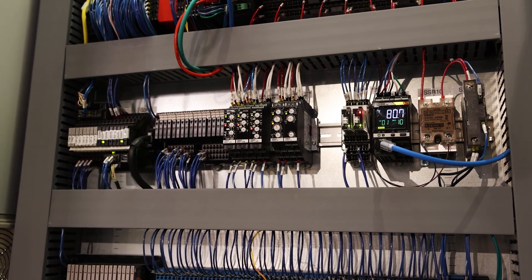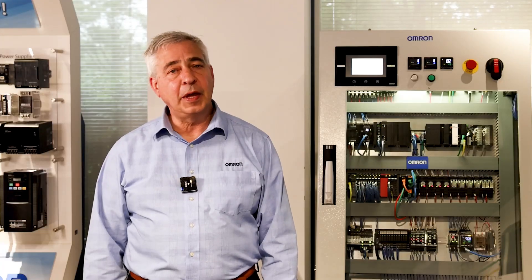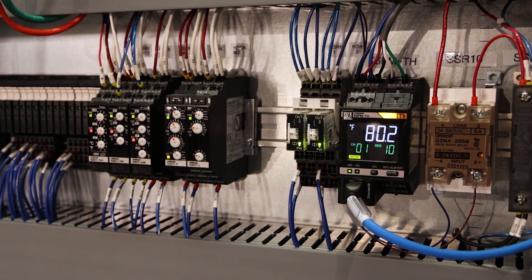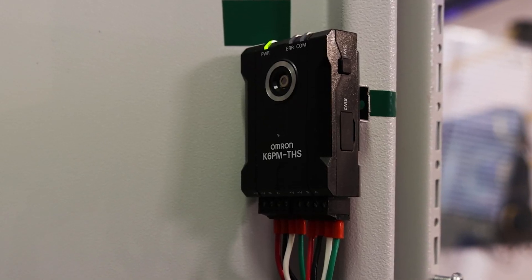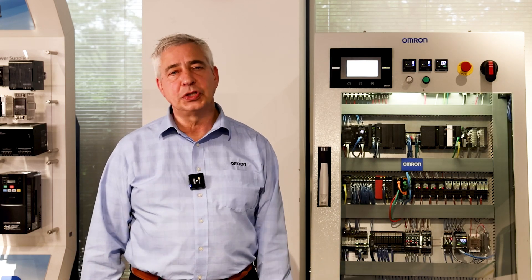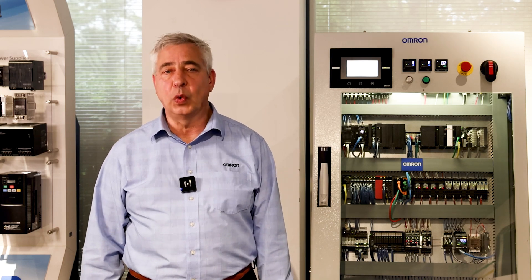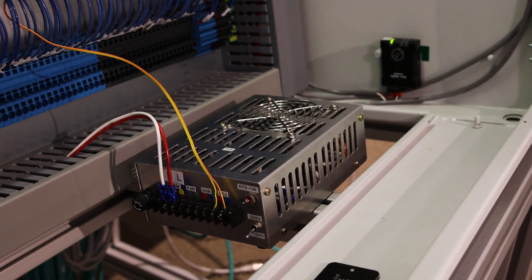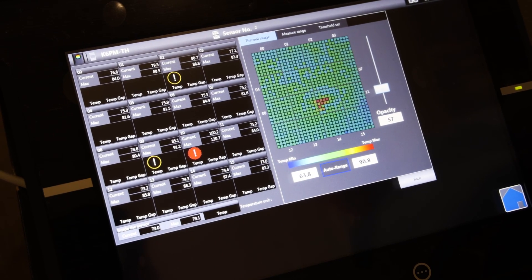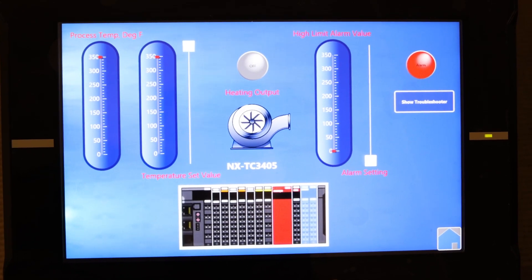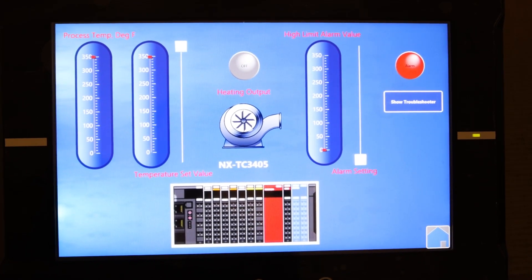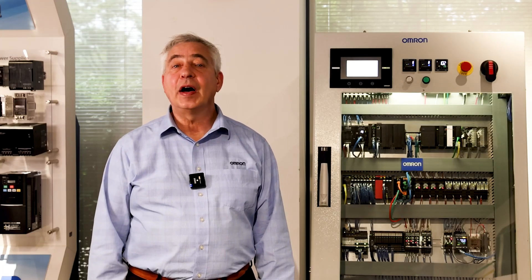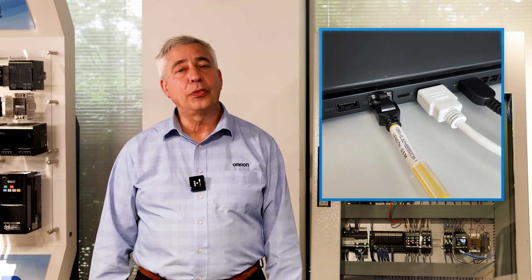The industrial controls in the demo panel are functional and generate heat. The internal panel temperature is monitored with a basic temp control and cooled if needed. In our panel, we have mounted and wired a K6PM-TH controller and two K6PM-THS thermal imaging cameras. Up to 31 cameras can be wired to a single controller, and the cameras can be placed 500 meters away. We use an NX-TC module with a solid-state relay and a heater element with thermocouple to create a hotspot. We use an NA5-HMI to control and display information. We've written a SysMac program to operate the heater, provide visual data, alarms, and heat images on the HMI using tagged data link and explicit messaging. We can access the program via Ethernet connection to our PC and run the thermal condition monitoring tool.